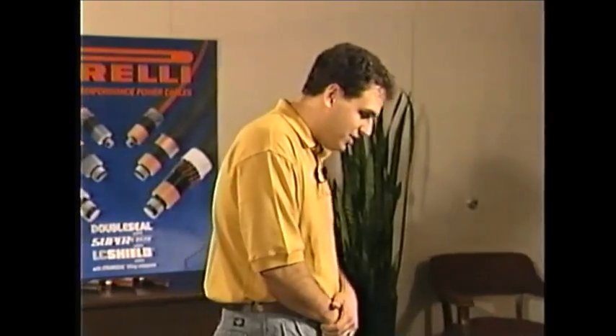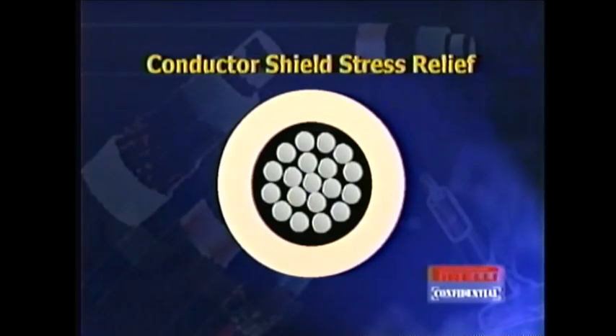So anywhere where you have a potential to have a void in that system, you want to try and avoid it. One of the ways that you do that, knowing that when you extrude a dielectric material over the conductor, you will not be able to extrude it so that all of the insulating material is in constant contact with the conductor, so you will have gaps. One of the ways that we avoid having those gaps and having the phenomenon of corona discharge at that very crucial interface is to put a semiconducting conductor shield and extrude it over the conductor, so you're filling in all of those voids with an air gap and creating a nice smooth interface.